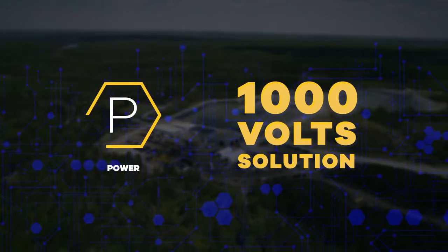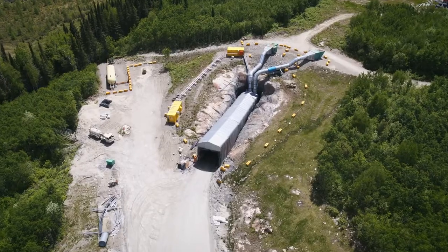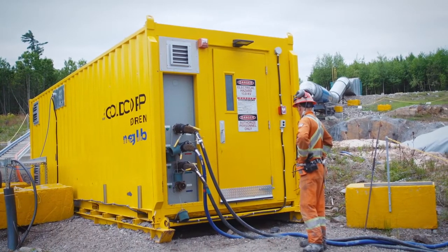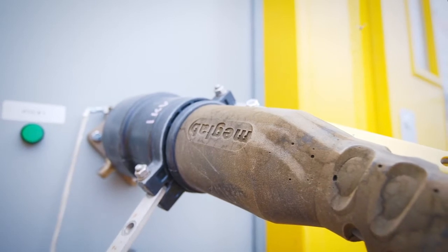For a long time, we've been thinking of having mines on a 1,000-volt standard. If you develop ramp access, having 1,000 volts allows a wider spread between your substations, so it's fairly economic in that sense. Cables will be smaller or will cover a much longer distance.